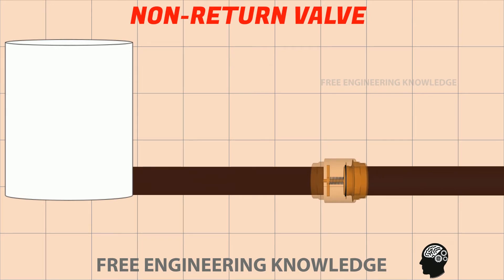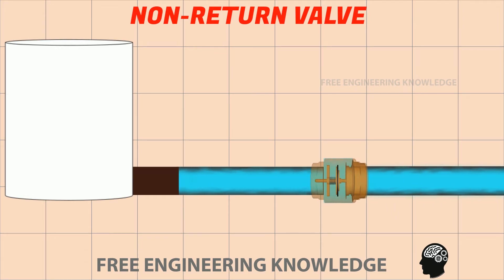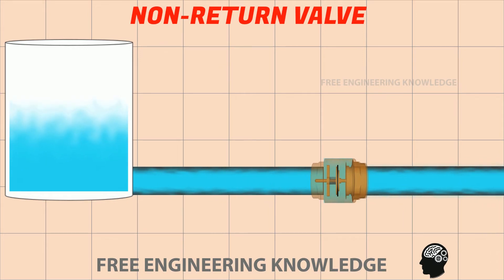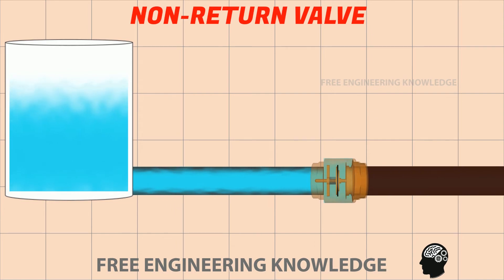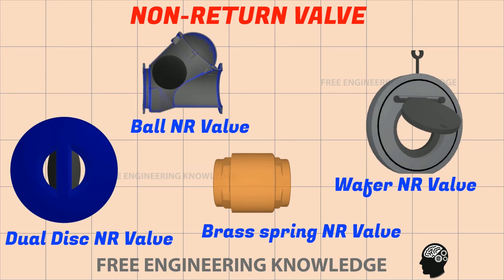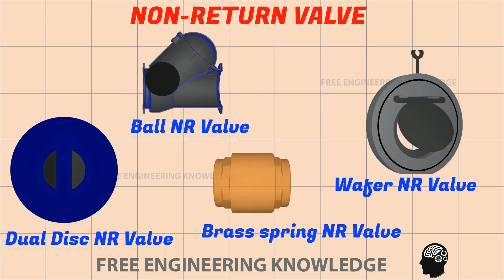When water enters through the inlet port of the non-return valve, the movable disc valve is pushed by the water pressure and the valve opens. Similarly, when water pressure drops at the inlet port, the movable disc valve is pushed back by the spring and the valve closes. In another video we will see the operating system of another type of non-return valve.